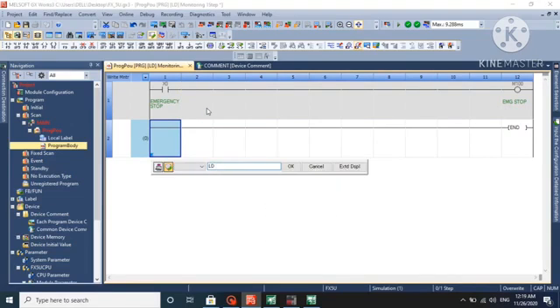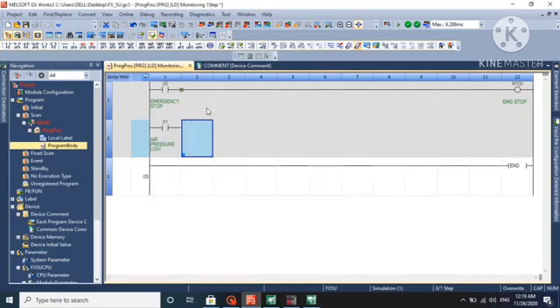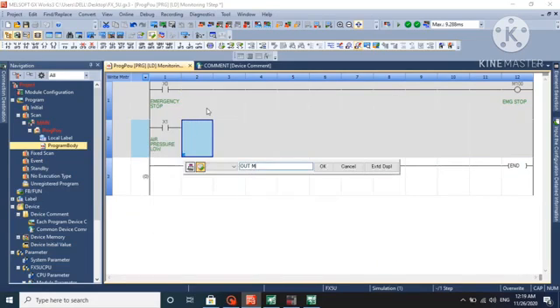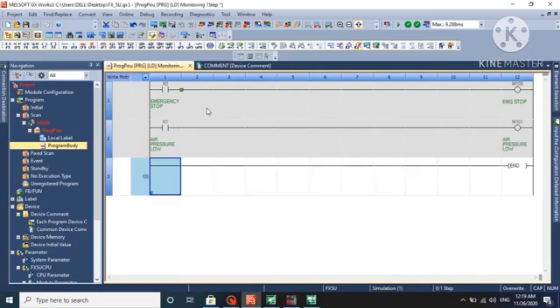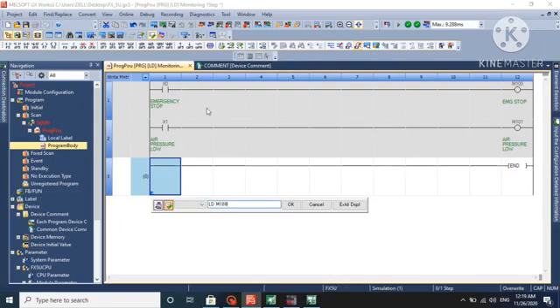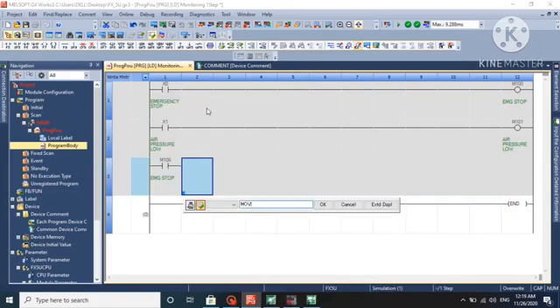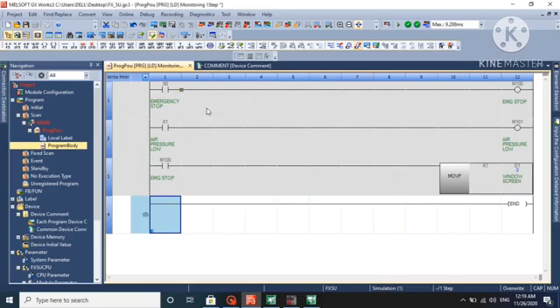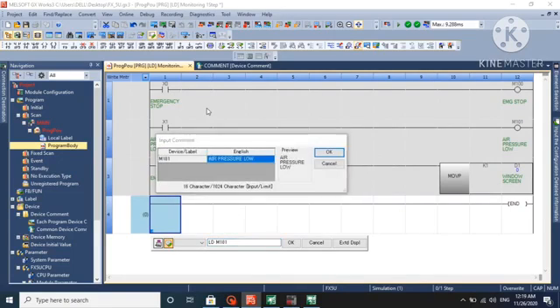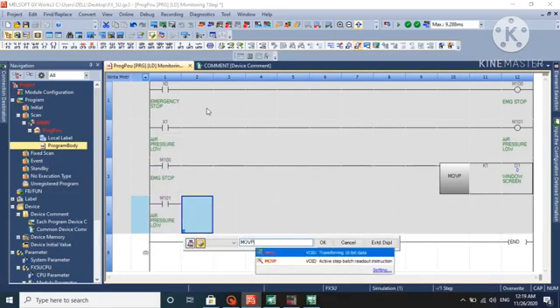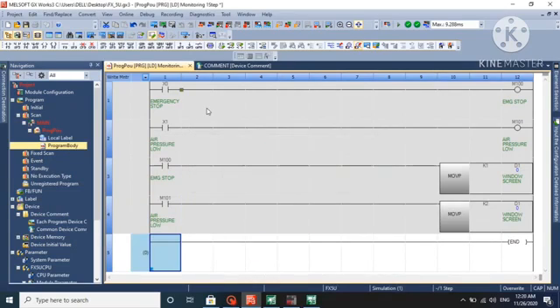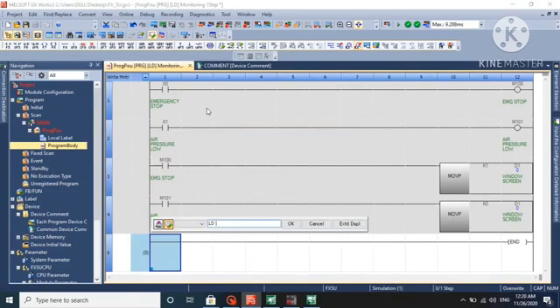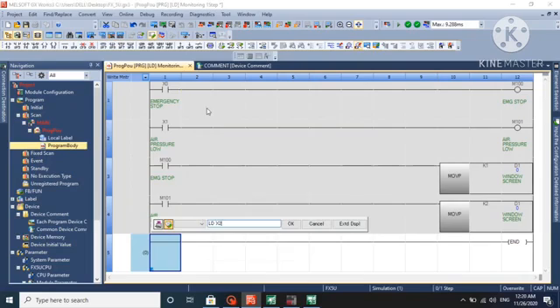Same, let's say NO contact of X1 is air pressure low. We'll create a flag M101 and name it air pressure low. Now when emergency is pressed, we'll move 1 to D1, as D1 is assigned as a window screen device in the HMI settings. Why K1? Because the screen which contains emergency stop text is screen number 1, and the screen with air pressure low is screen number 2.